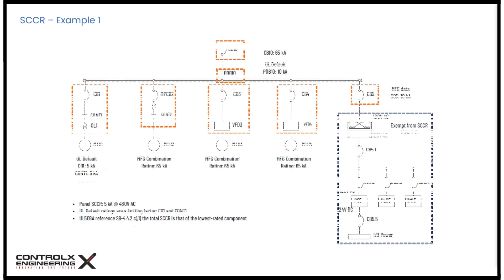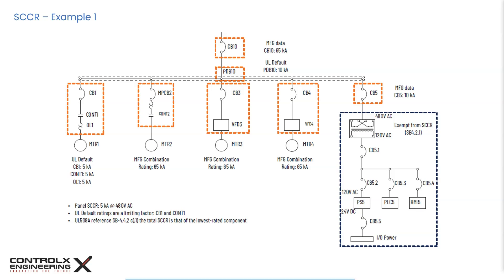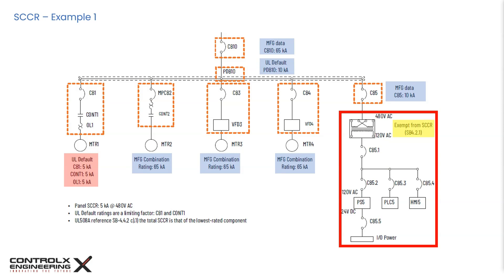These examples are taken from an Allen-Bradley publication. The first wiring diagram shows a motor control circuit with breakers, overload protection devices, and contactors on the 480V side, as well as 120V and 24V circuits after a step-down transformer. Steps 1 and 2 identify component SCCRs and current limiting devices. Per UL 508A paragraph SB 4.2.1, the low-voltage section is exempt from SCCR. Per paragraph SB 4.4.2, the lowest component SCCR determines the overall panel SCCR — in this case, motor 1's circuit with CB1 and contactor 1 having ratings of 5 kA — so the panel SCCR is 5 kA at 480V.